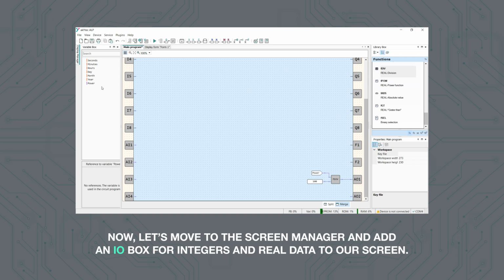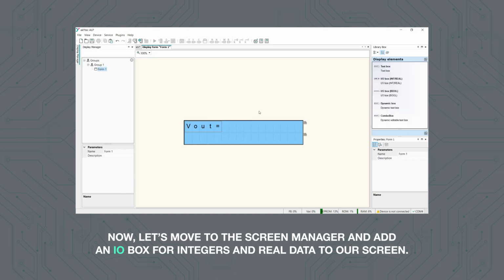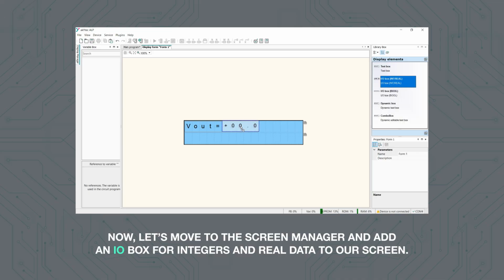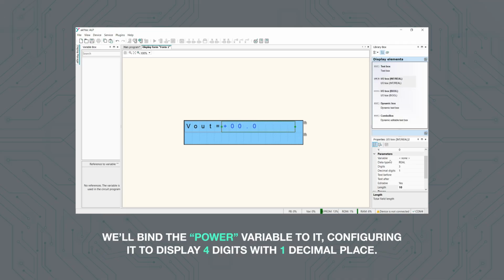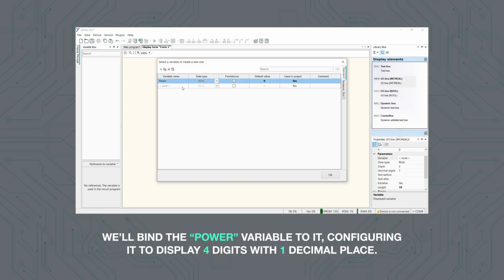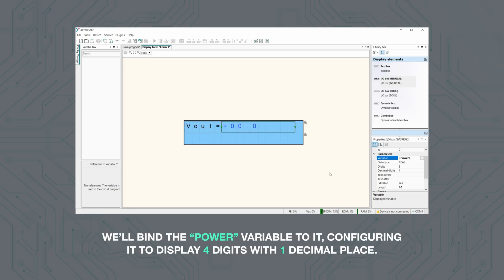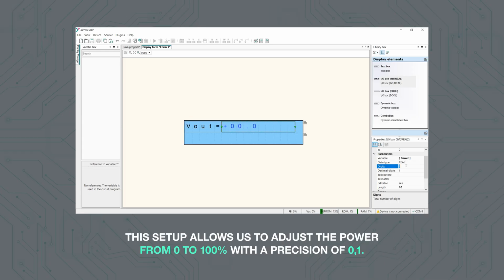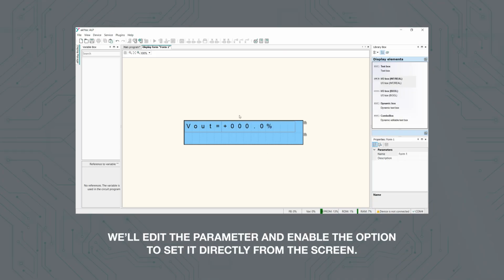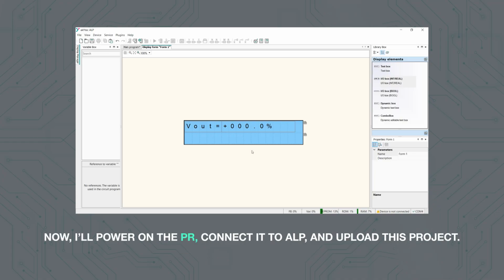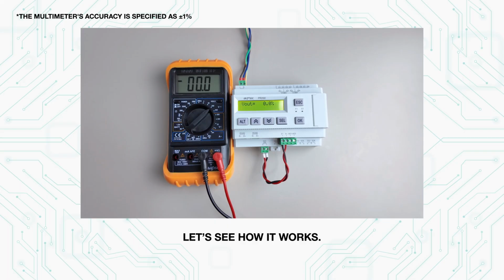Now, let's move to the Screen Manager and add an I/O box for integers and real data to our screen. We'll bind the power variable to it, configuring it to display 4 digits with 1 decimal place. This setup allows us to adjust the power from 0 to 100% with a precision of 0.1. We'll edit the parameter and enable the option to set it directly from the screen. Now, I'll power on the PR, connect it to ALP and upload this project. Let's see how it works.